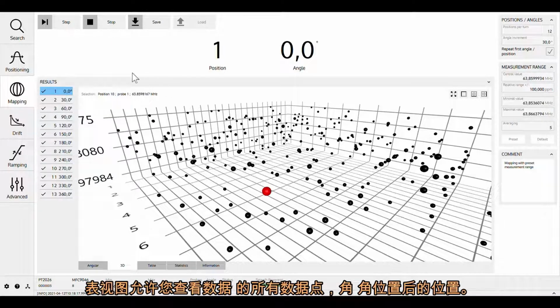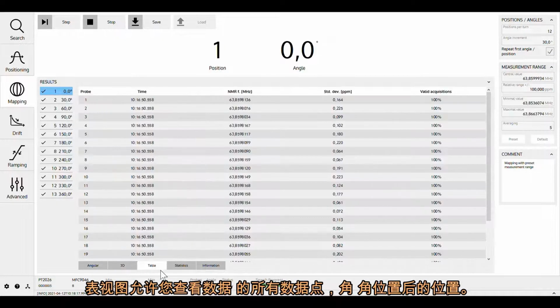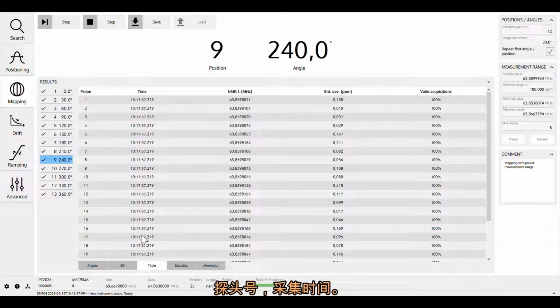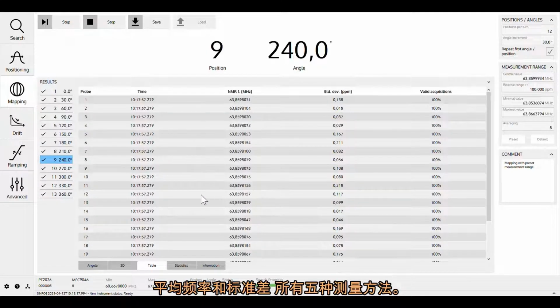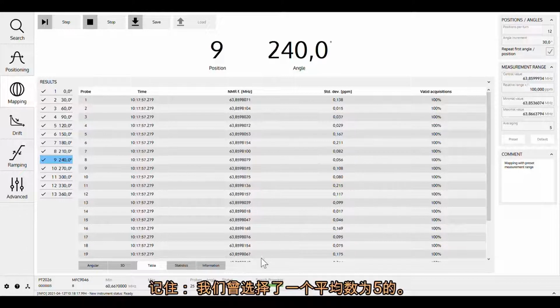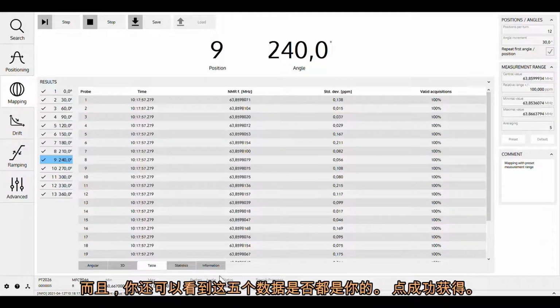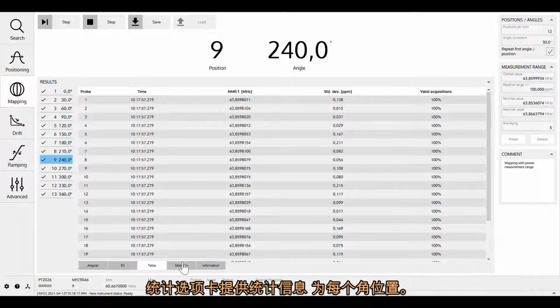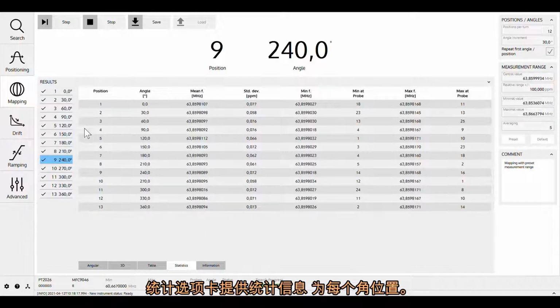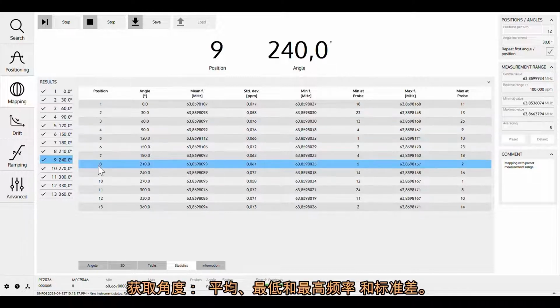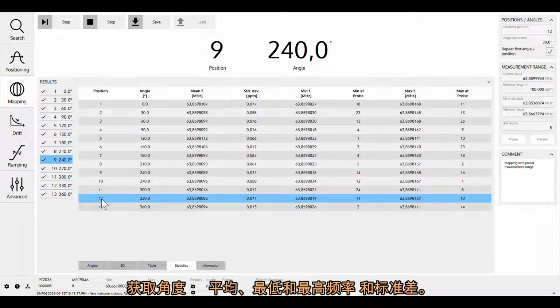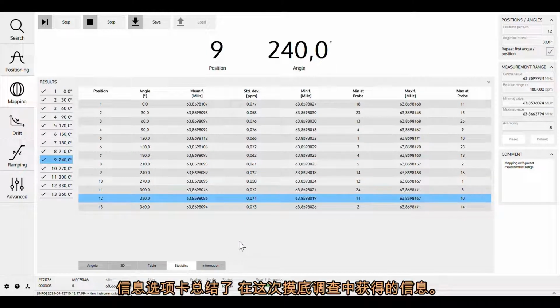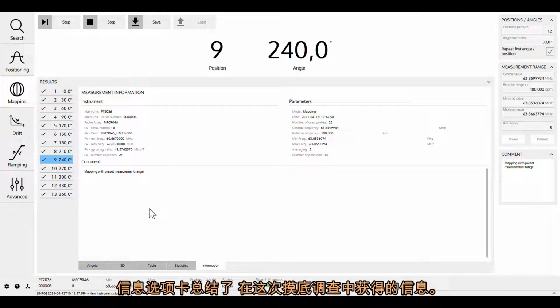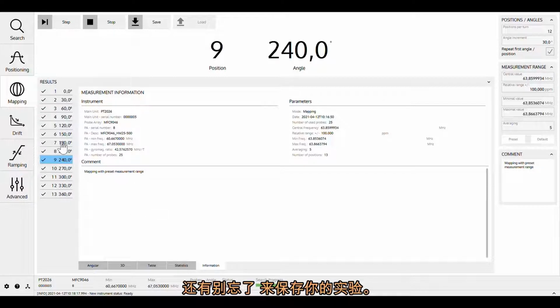The table view allows you to see the data of all data points, angular position after angular position. The probe number, the time of acquisition, average frequency and standard deviation for all 5 measurements. Remember we had selected an averaging of 5. And also you can see if all 5 data points were acquired successfully. The Statistics tab offers the statistical information for each of the angular position, angle of acquisition, mean, minimum and maximum frequencies, and standard deviation. The Information tab summarizes the information acquired during this mapping. And also, don't forget to save your experiment.